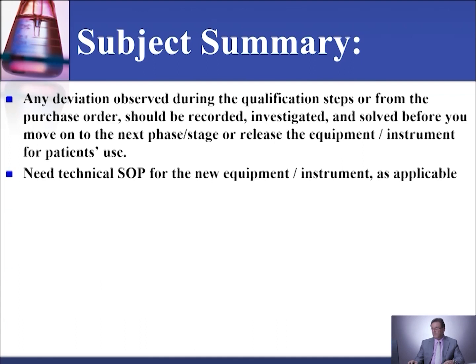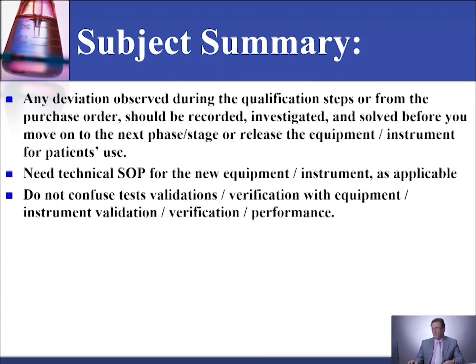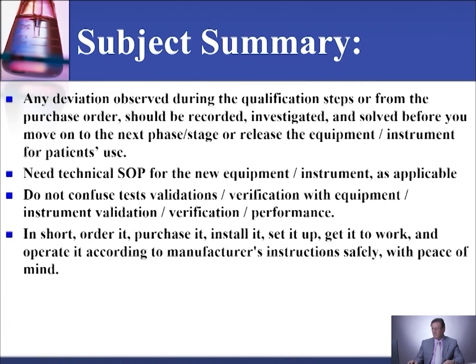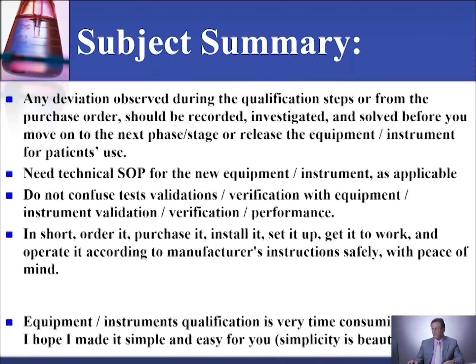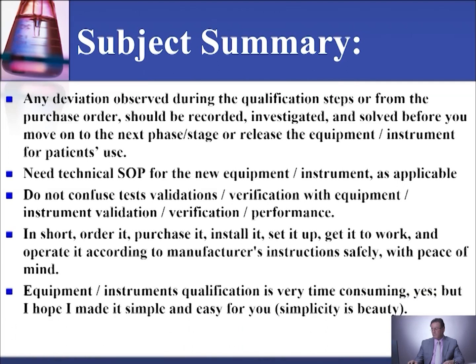You need technical SOPs for the new equipment or instrument as applicable. Do not confuse test validation and verification with equipment or instrument validation and verification of performance. The test validation and verification is part of the equipment or instrument verification. In short, order it, purchase it, install it, set it up, get it to work, and operate it according to the manufacturer's instructions, safely and with peace of mind. Equipment and instrument qualification is a very time-consuming process, yes, but I hope I made it simple and easy for you. Simplicity is a beauty.